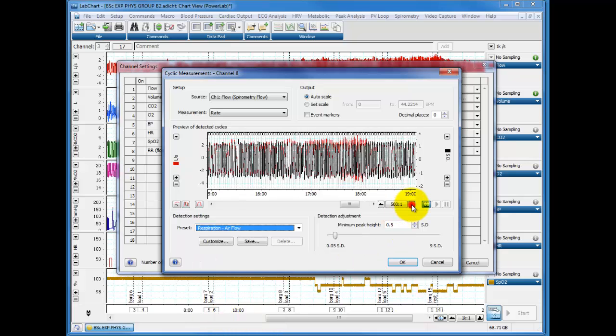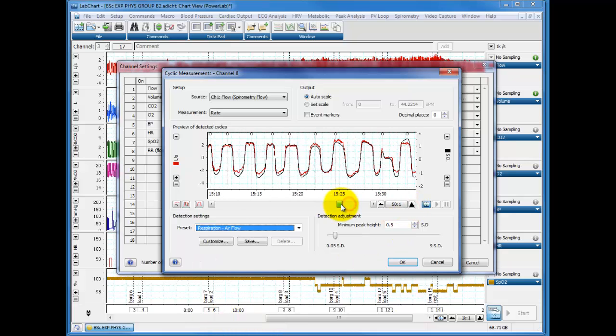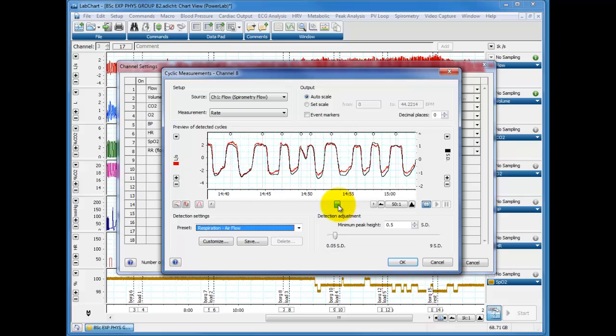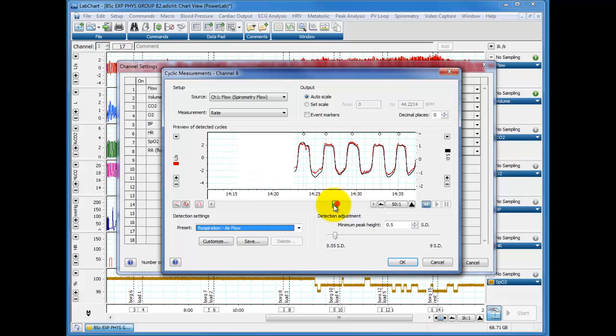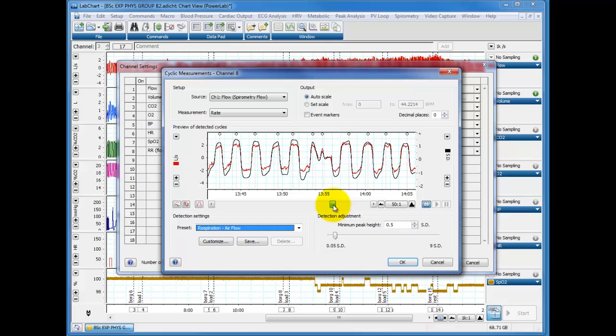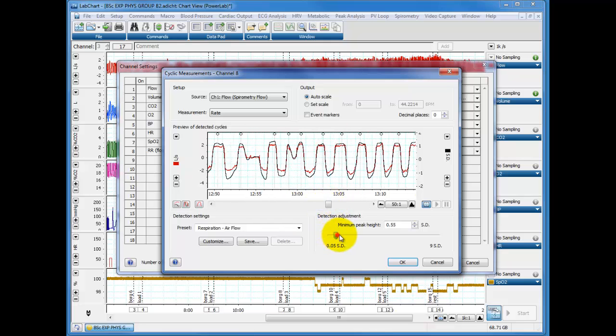And in the preset here we scroll down until we see respiratory air flow. And then just have a little zoom in and make sure that it's picking up all the peaks. It's picking up a double peak but that is a double breath so we'll leave that as it is. There's a double breath so just make sure that's working and that's all good.